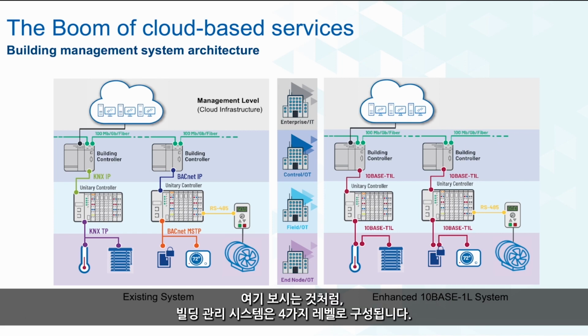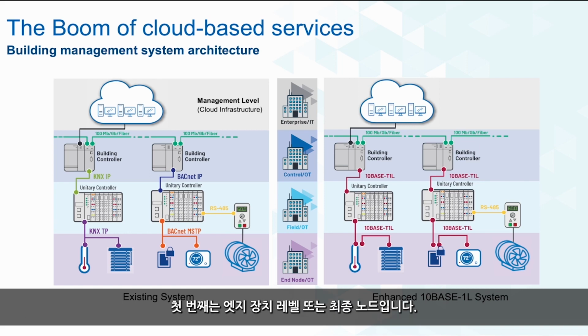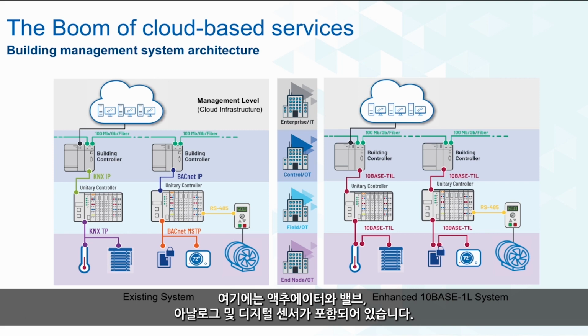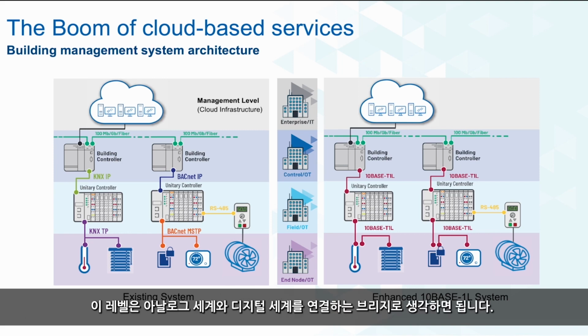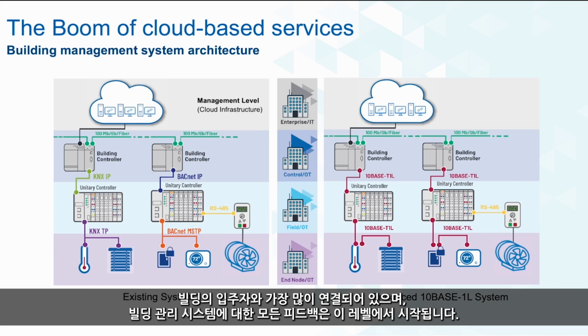As you can see here, the building management system is composed of 4 levels. First, you have the edge device level, or end nodes. It contains actuators, valves, analog and digital sensors. We can consider this level as the bridge between the analog and digital worlds, and it's the most connected with the occupants of buildings, which makes sense, as all feedback to the building management system starts at this level.